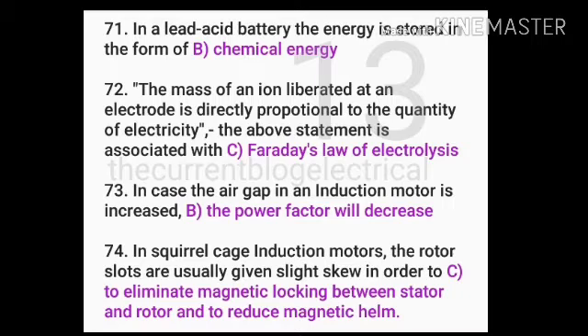In the case of an induction motor, if the air gap is increased, the power factor will decrease. In squirrel cage induction motors, the rotor slots are usually given a slight skew in order to eliminate magnetic locking between the stator and rotor and to reduce harmonic effects.